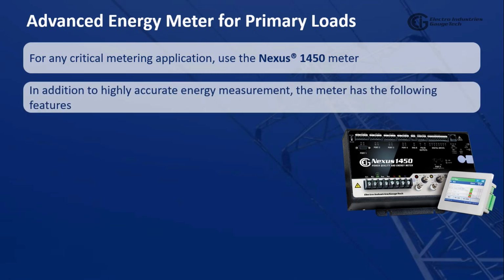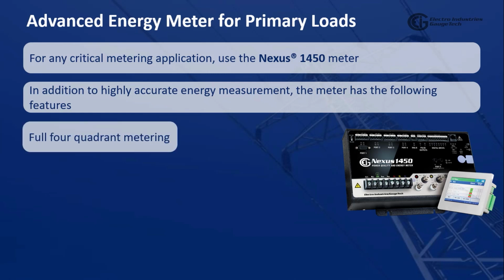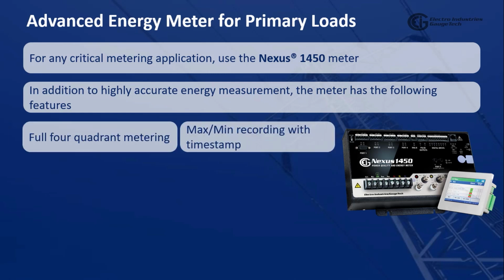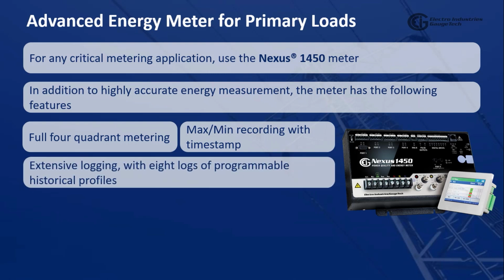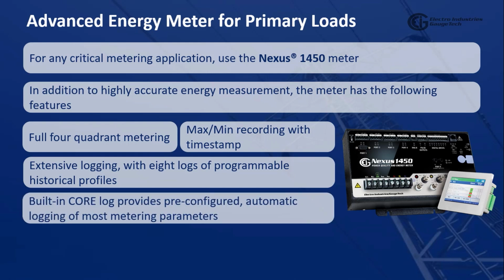In addition to highly accurate energy measurement, the meter has the following features: full 4-quadrant metering, max/min recording with timestamp, extensive logging, with 8 logs of programmable historical profiles. Built-in core log provides pre-configured, automatic logging of most metering parameters.